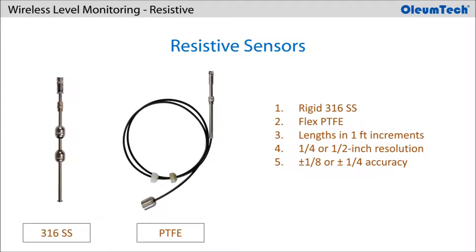OleumTech resistive sensors are offered in both rigid 316 stainless steel and flexible polytetrafluoroethylene (PTFE) type in variable lengths in 1-foot increments. There are ¼-inch and ½-inch resolution options for the sensors, providing ±1/8-inch or ¼-inch accuracy respectively.